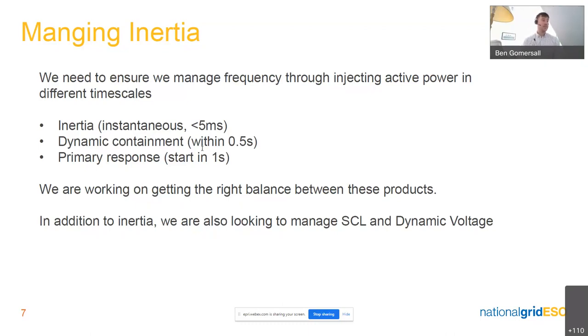The final thing I wanted to say on this is that whilst we're talking about inertia today, the driver causing the decline of inertia on the system, which is the decline of synchronous generation, is also causing a decline in short circuit level, dynamic voltage and system strength. So when we are looking at solutions, and I would encourage other network operators around the world to do this, we should look at these holistically, looking for solutions that address all three together rather than addressing the inertia and then looking at the others.